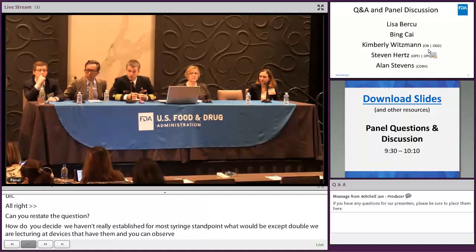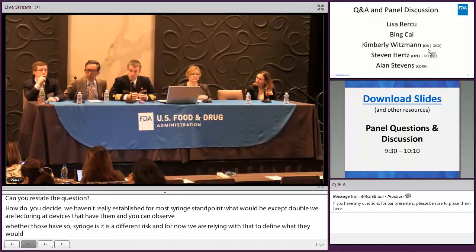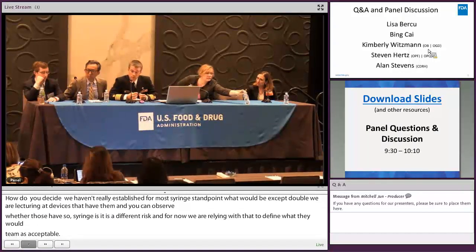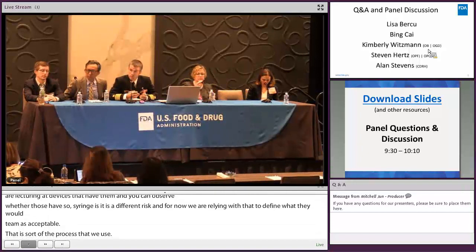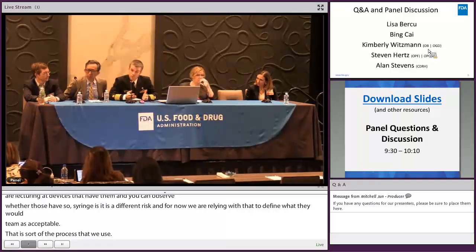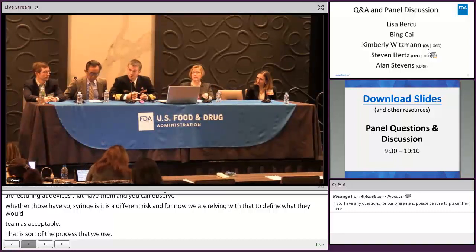That's sort of the process that we use. I would refer you to ISO 14971, which is a risk management standard for medical devices. It has examples of levels of risk depending on levels of severity, and that's one of the things we've relied on when doing our reviews and making these decisions.